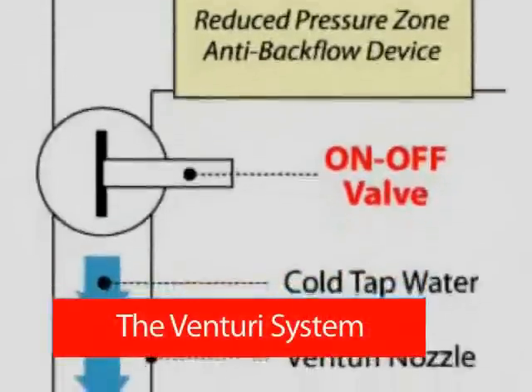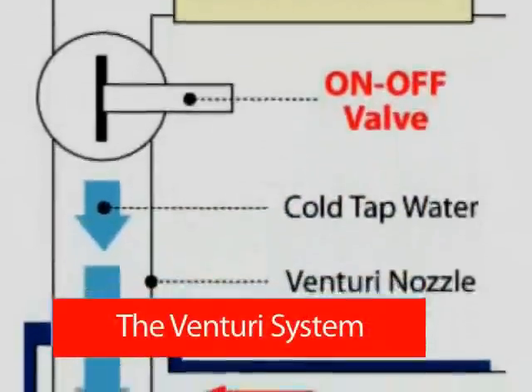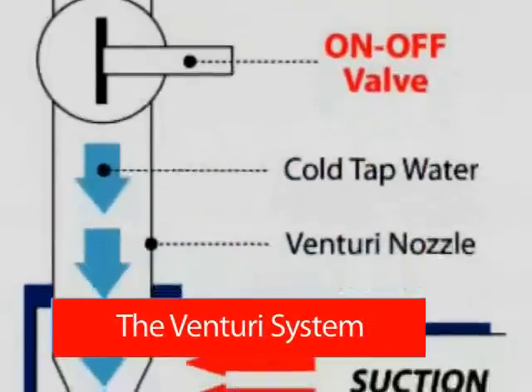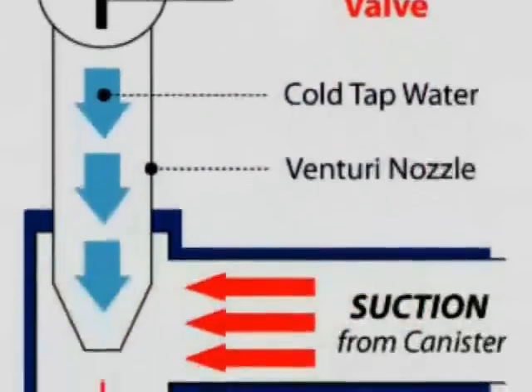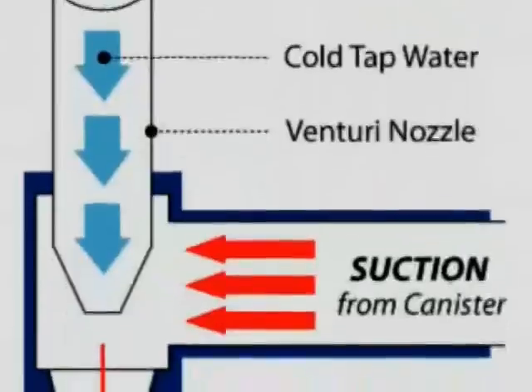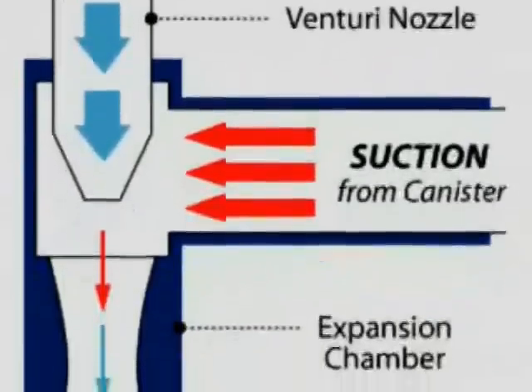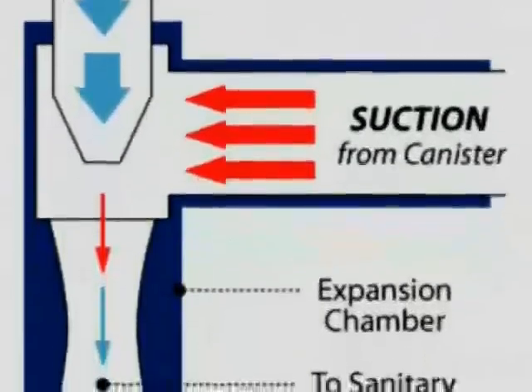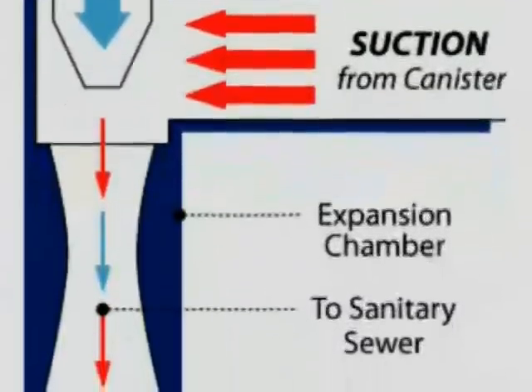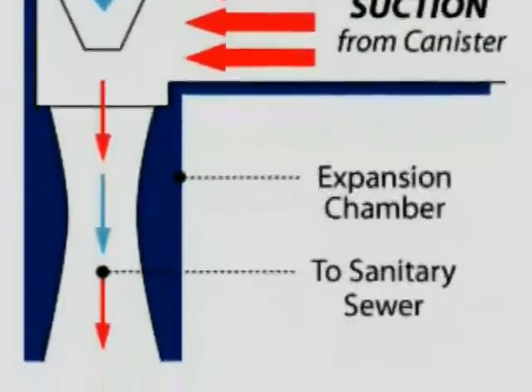The disposal device we are speaking of operates via a Venturi system. The Venturi system uses water flow to operate the device — the device is powered by tap water. The device is designed to dispose of infectious liquid medical waste from a suction canister.